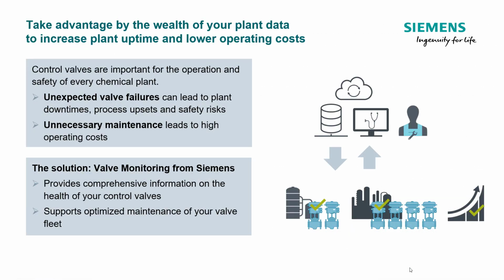As I alluded to, what we're trying to do is to get this intelligent data up to a platform that can analyze the log data over prolonged periods. So what we're trying to do here is really predict when a valve is going to fail. That is what is classed as preventive maintenance. What you can do to establish preventive maintenance is just maintain the valves all the time, and that comes into the category of unnecessary maintenance, and that again can be costly and time consuming.